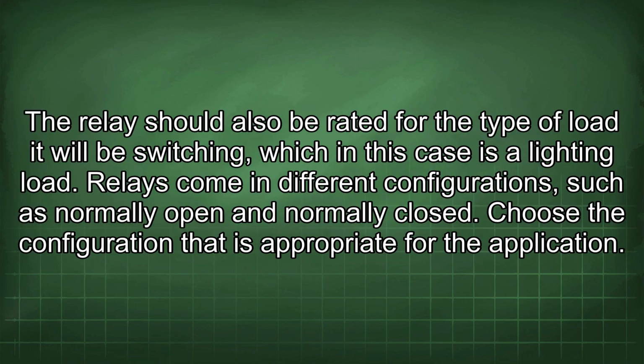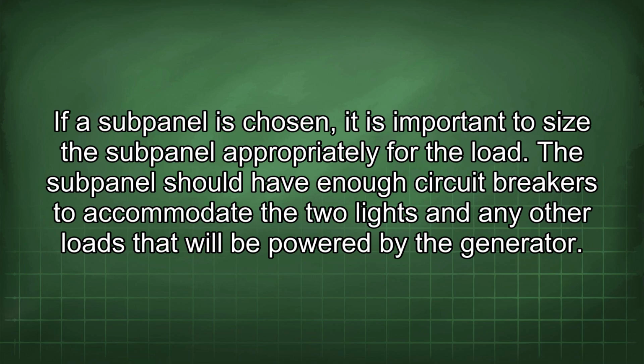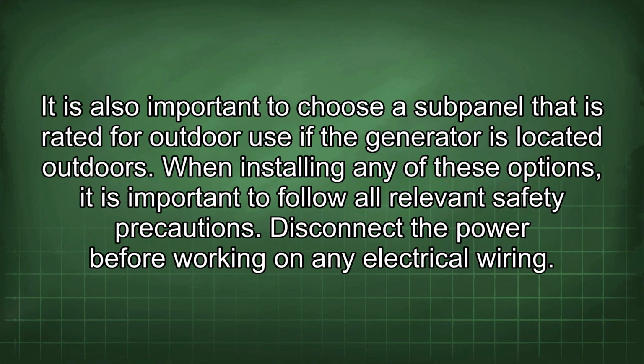The relay should also be rated for the type of load it will be switching, which in this case is a lighting load. Relays come in different configurations such as normally open and normally closed. Choose the configuration that is appropriate for the application. If a subpanel is chosen, it is important to size the subpanel appropriately for the load. The subpanel should have enough circuit breakers to accommodate the two lights and any other loads that will be powered by the generator. It is also important to choose a subpanel that is rated for outdoor use if the generator is located outdoors. When installing any of these options, it is important to follow all relevant safety precautions.